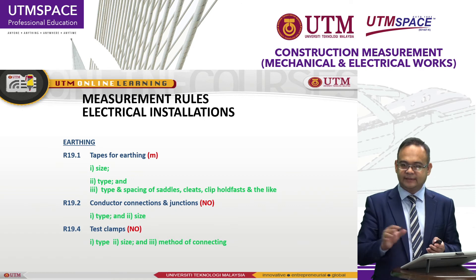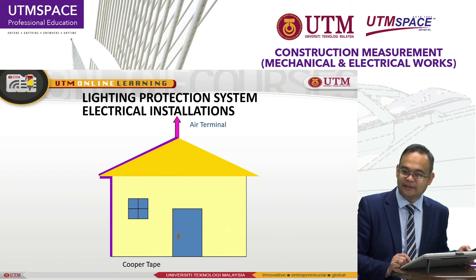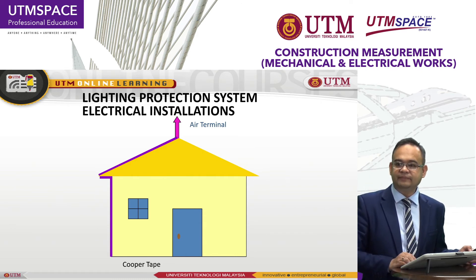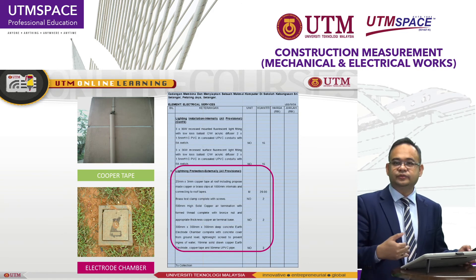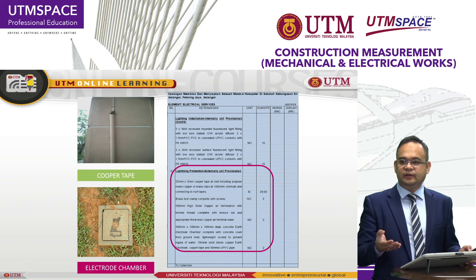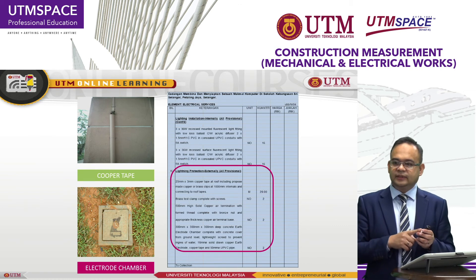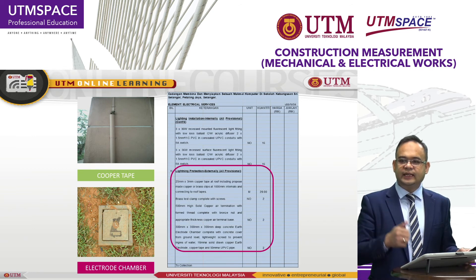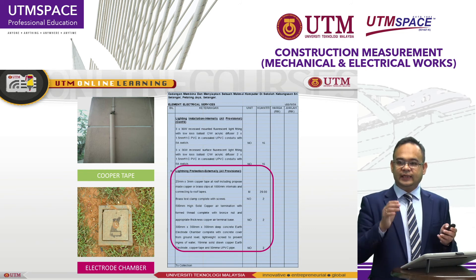Normally, when we want to do the testing and commissioning, we need to test the workability of this lightning protection system using a test clamp. At the top is the air terminal, connected to the building using a copper tape, and then brought to the nearest soil — what we call the electrode pit or chamber. In a Bill of Quantities, we have four main items: first, the air terminal; second, the copper tape; third, the earth electrode chamber; and fourth, the test clamp. These are the four main components of the lightning protection system.